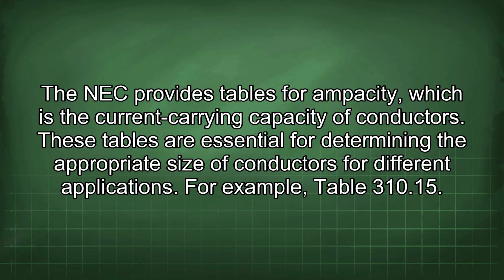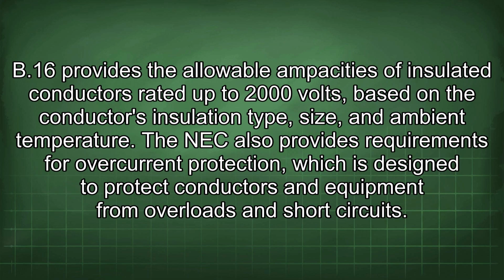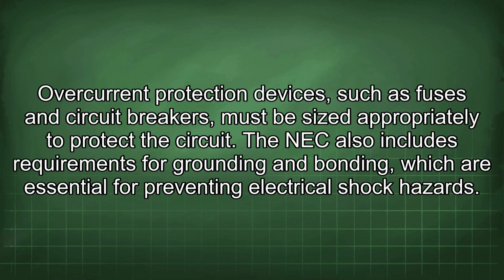For example, Table 310.15(B)(16) provides the allowable ampacities of insulated conductors rated up to 2000 volts based on the conductor's insulation type, size, and ambient temperature. The NEC also provides requirements for overcurrent protection, which is designed to protect conductors and equipment from overloads and short circuits. Overcurrent protection devices, such as fuses and circuit breakers, must be sized appropriately to protect the circuit.